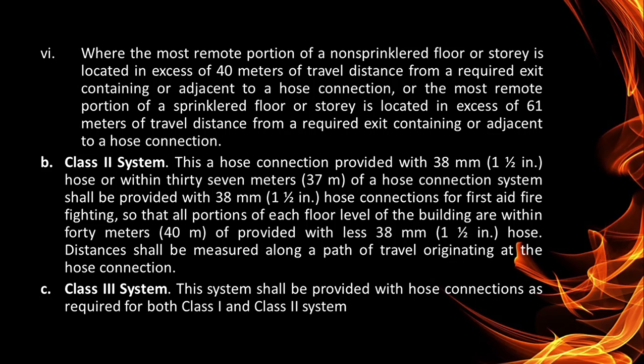Next is the Class 2 system. This is a hose connection provided with 38 mm or 1 1/2 inch hose, within 37 meters of a hose connection system, provided with 38 millimeter hose connection for first aid firefighting, so that all portions of each floor level of the building are within 40 meters of a hose connection provided with a 38 mm hose. Distances shall be measured along a path of travel originating at the hose connection. So, Class 3 system. This system shall be provided with hose connection as required for both Class 1 and Class 2 system.